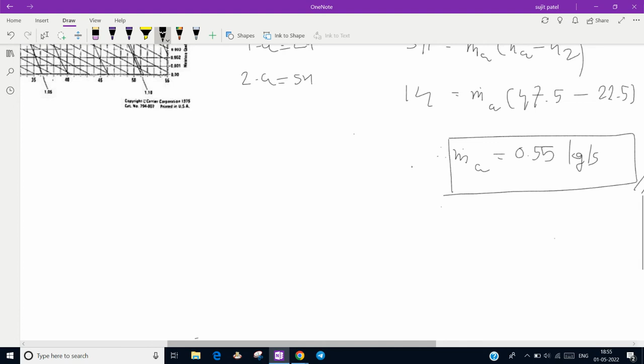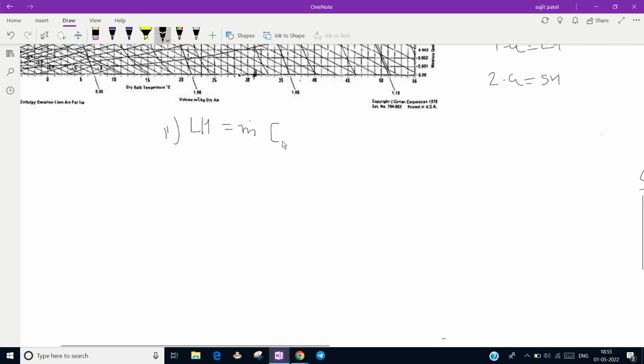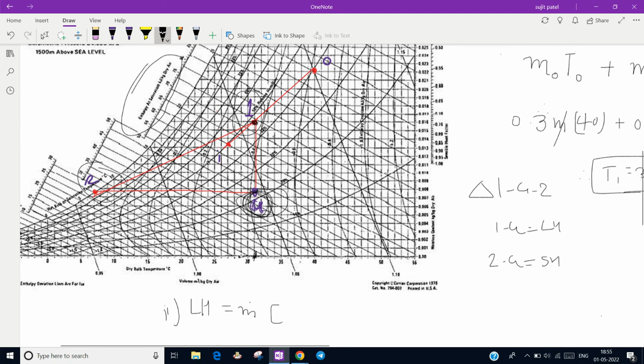So the first question is solved. Now the second question is latent heat. Latent heat is m dot, mass of the air, into H1 minus HA. From the triangle, it is H1 minus HA. From the psychrometric chart, the mass flow rate is 0.55, H1 is about 65, and HA is 47.5. When you solve this, you get 9.625 kilowatt. This is the latent heat, the answer of our second question.